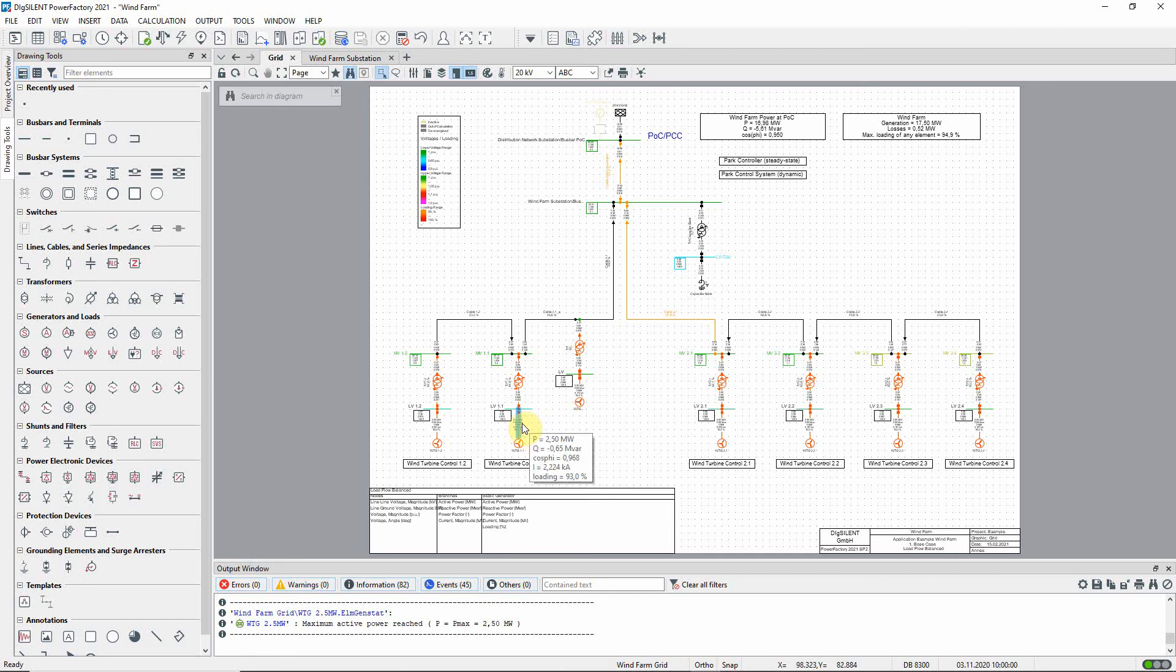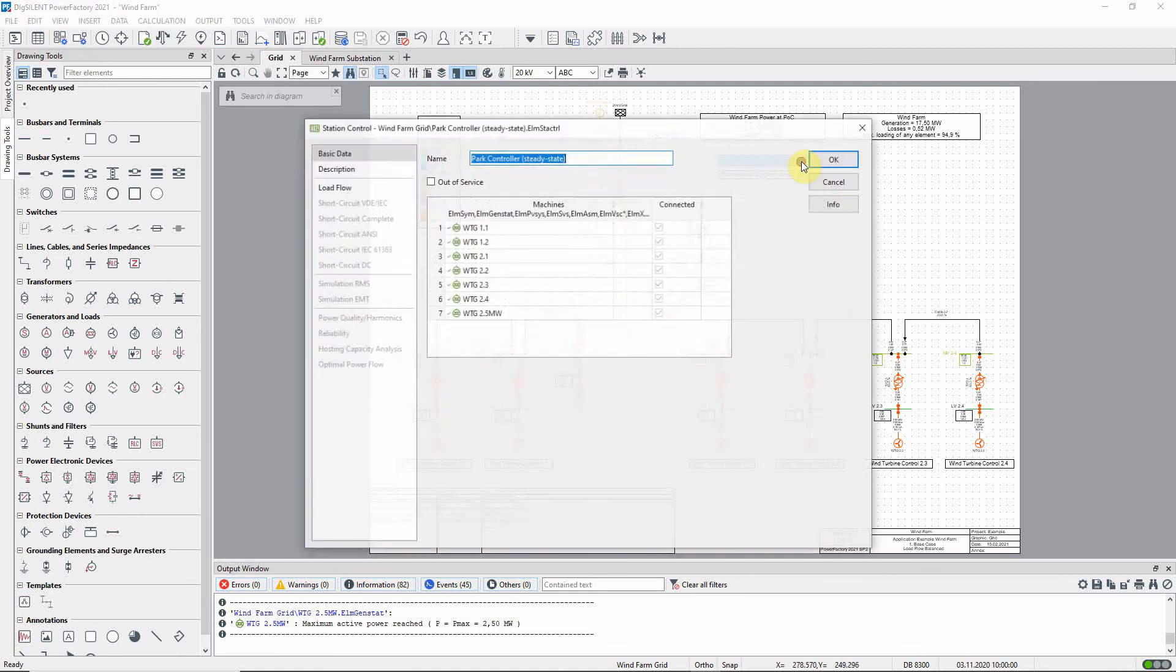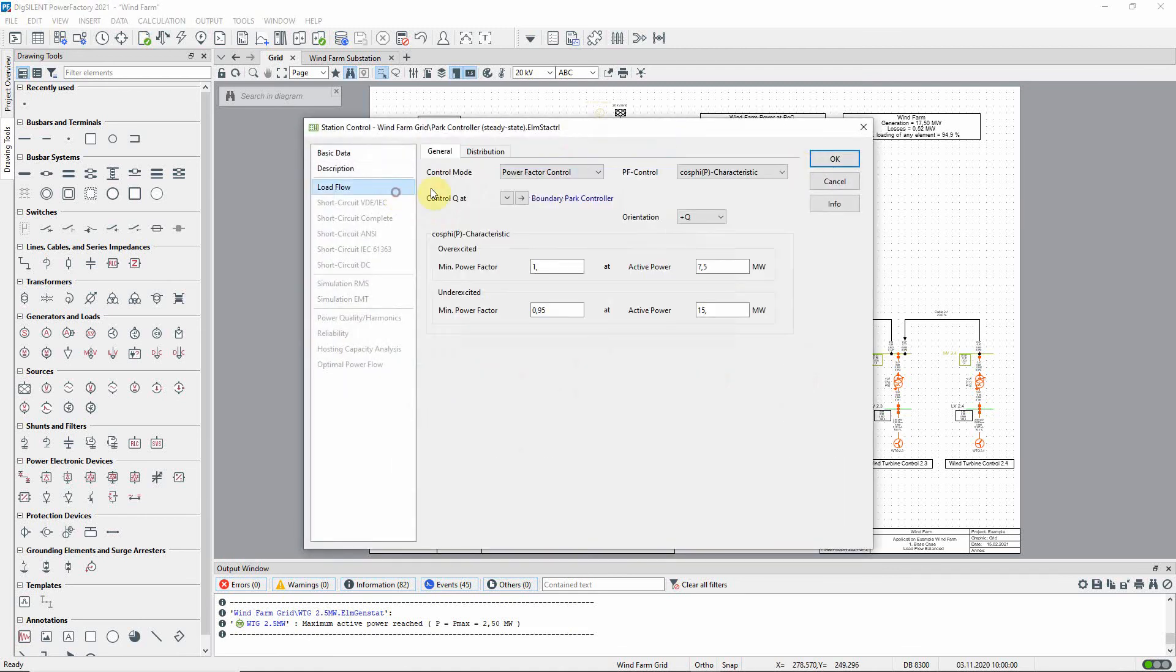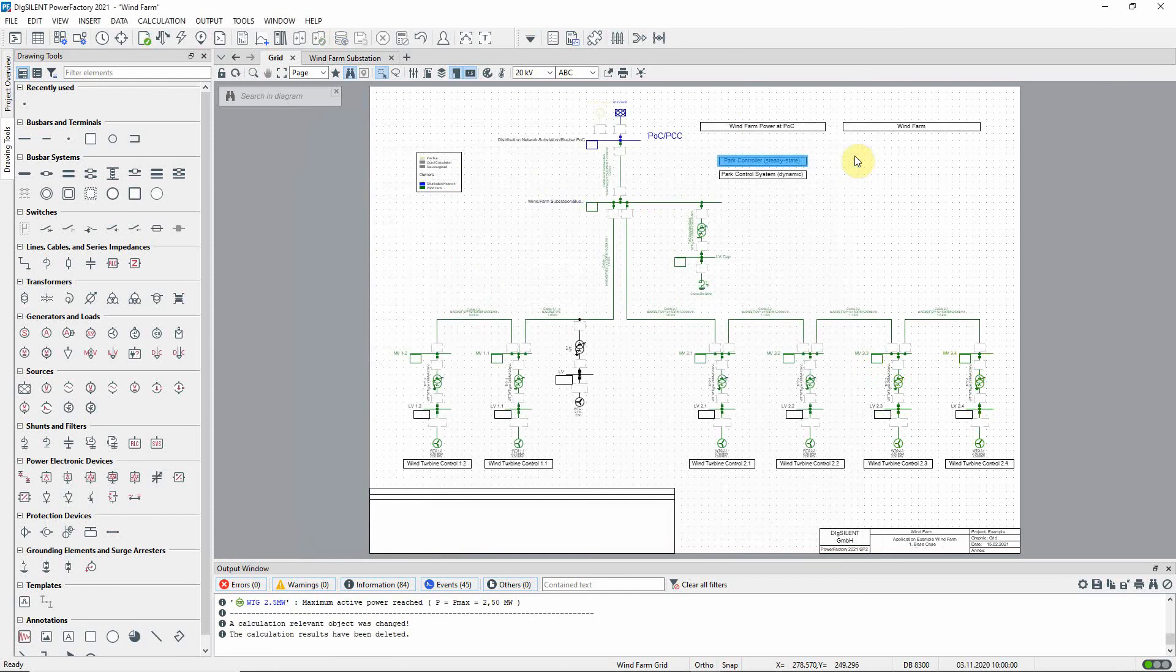Since we have introduced the new generator, we should update the parameters in the cos phi as a function of P characteristic. Let us increase the active power to 17.5 megawatts to reflect the new nominal power of the wind farm and rerun the load flow.